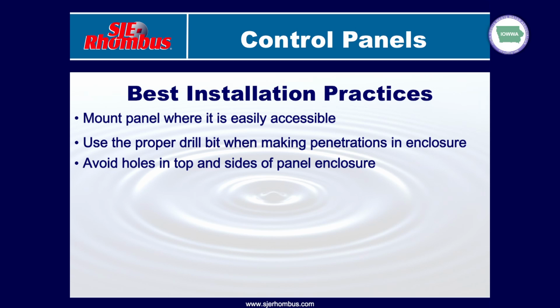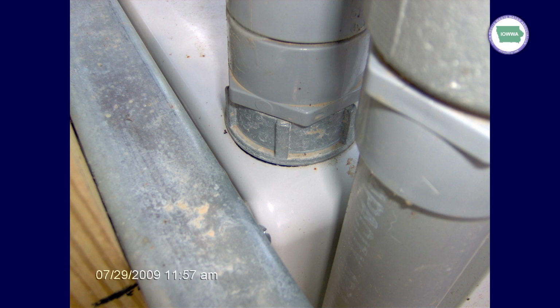As I mentioned already, anytime you penetrate the enclosure, you're eating into the NEMA rating on the control panel enclosure. So we want to make sure that you use fittings, penetrations that are sized properly for the holes that you drilled through the panel with. We want to avoid holes in the top of the panel and the sides of the panel. Gravity is going to work against us if we've got penetrations in the top of the panel or the sides of the panel as precipitation runs down on the control panel.